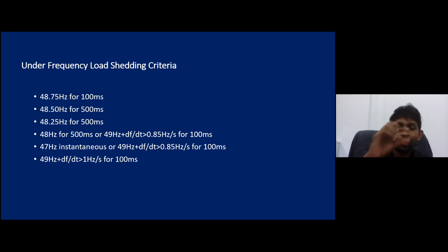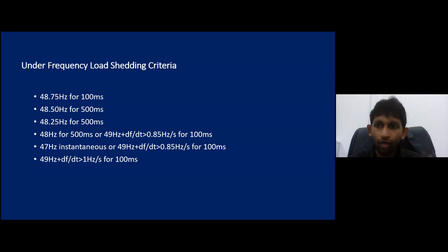There are 31.5 transformers, then 9 feeders. Now these 9 feeders are being programmed. One feeder is programmed for the first load shedding, the second one is for the second load shedding. There's a program for frequency load shedding. So when it detects one of these criteria, it shuts down that feeder. That's what happens in reality. In PSSE, what we do is, at 48.75, we approximately know the order of load that can be taken out of the system by the load shedding criteria. That's what is simulated in PSSE.